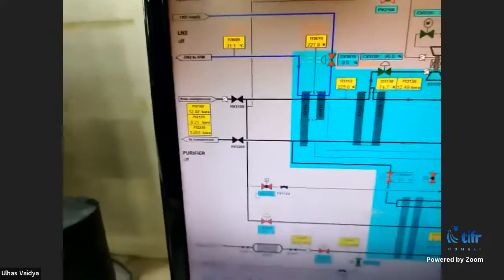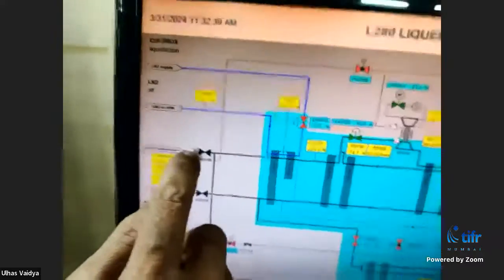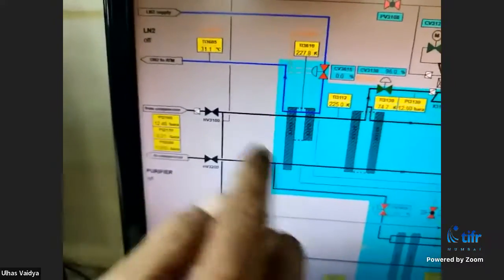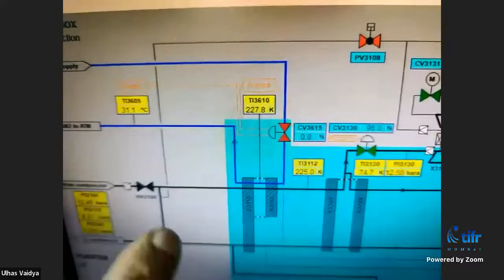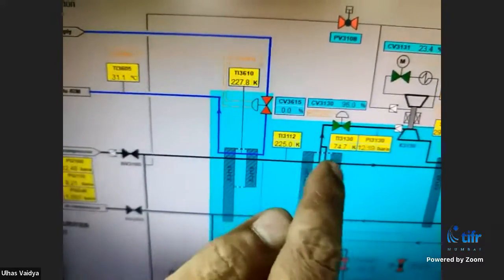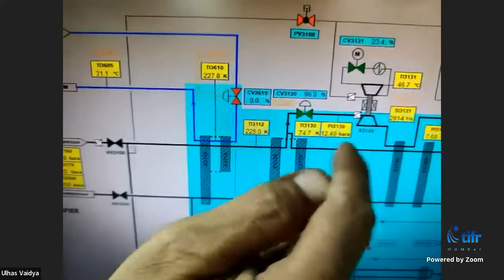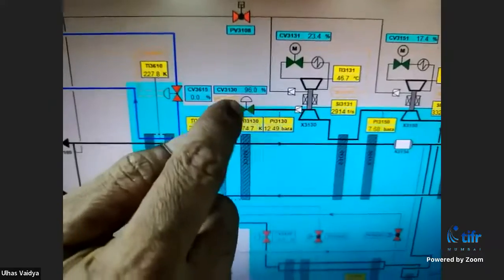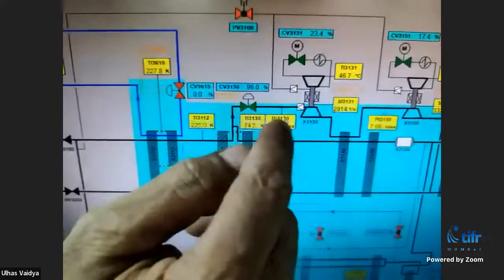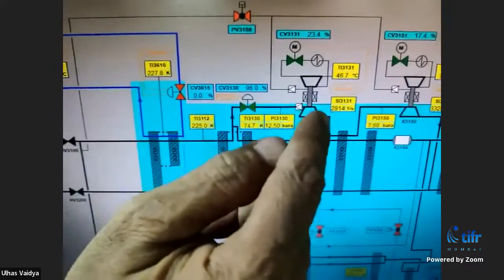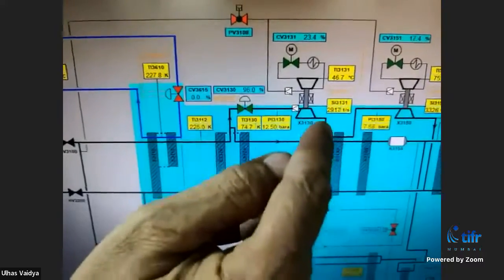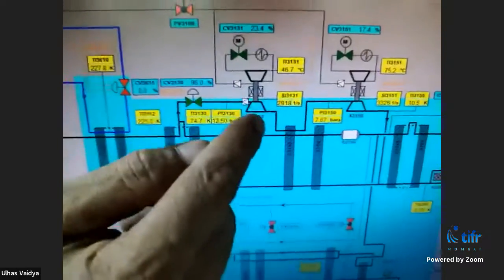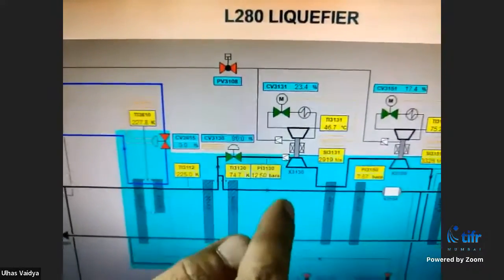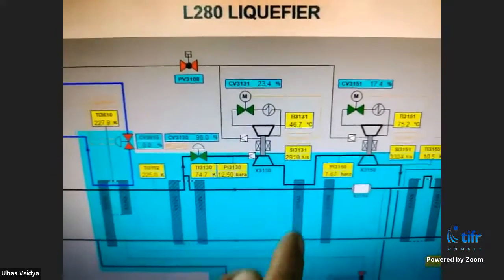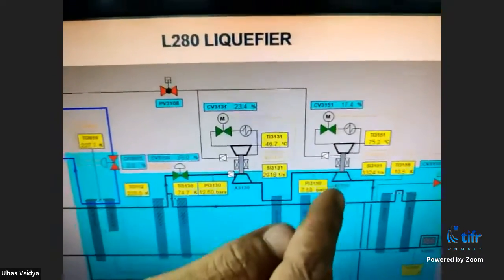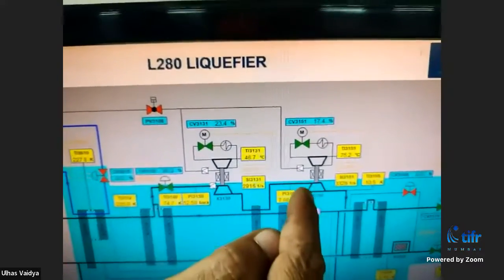First let's see how the system works. This is incoming gas, which cools down through a series of heat exchangers. The incoming gas passes through these and is divided into two parts: 20% goes straight for liquefaction, and 80% goes for expansion in the turbine. Here is the turbine expander, which expands the gas, cooling it down, then it goes to the second heat exchanger, reaching about minus 200 degrees Celsius. That cold is absorbed by this heat exchanger, and the gas then proceeds to the second turbine, where it cools further down to minus 263 degrees Celsius.